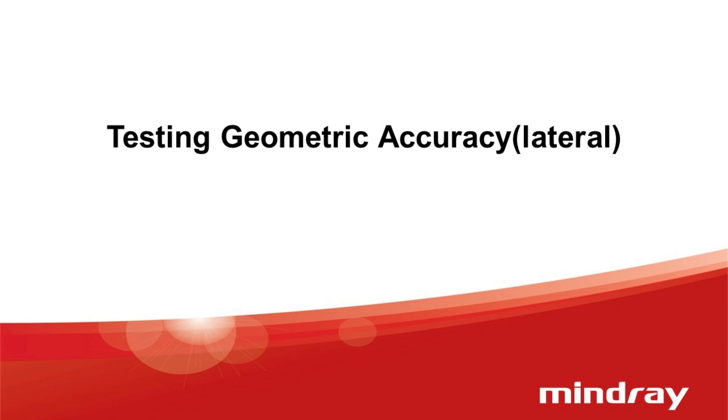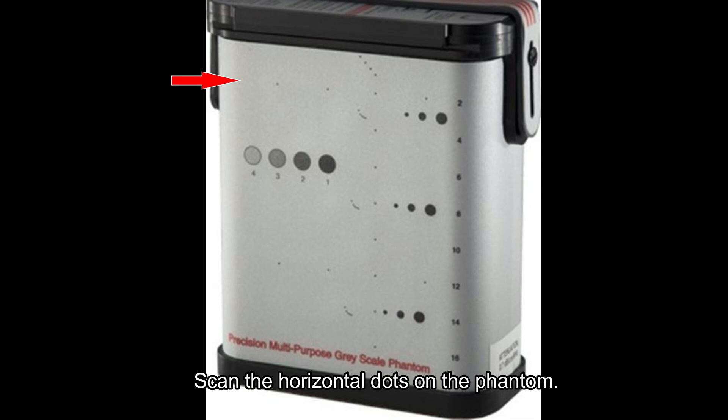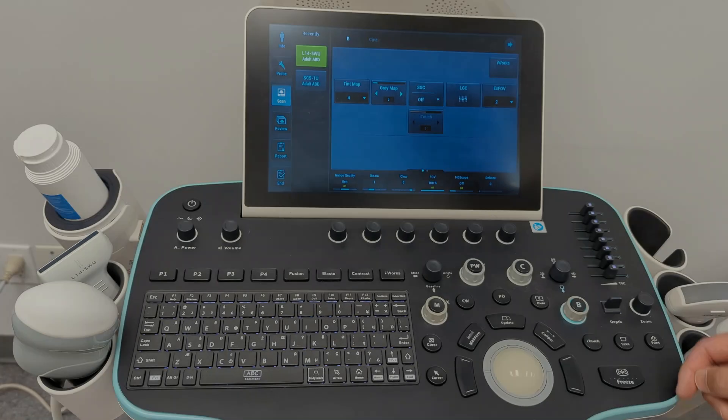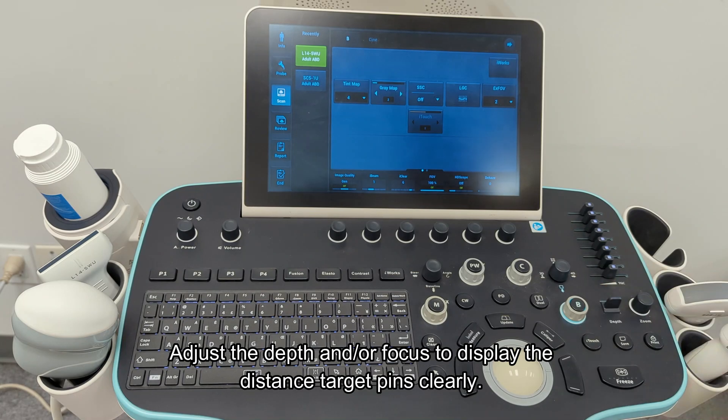Testing geometric accuracy: lateral. Scan the horizontal dots on the phantom. The lateral targets on the Gammex 403GS-LE are 30 millimeters apart. Adjust the depth and/or focus to display the distance target pins clearly.